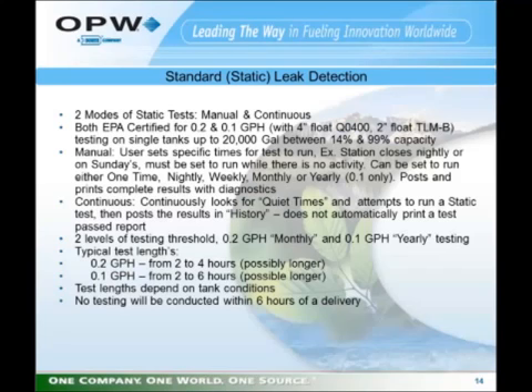Continuous static leak detection means that the unit is monitoring the tank. When it sees that the tank is idle, it will then launch a static leak test automatically. If the tank goes active during the test, it will abort the test, wait for the tank to go idle again, and begin a new static test. If the tank is inactive during the entire period of the test, at the end of the test it will post a result to history, but it will not print out a result.